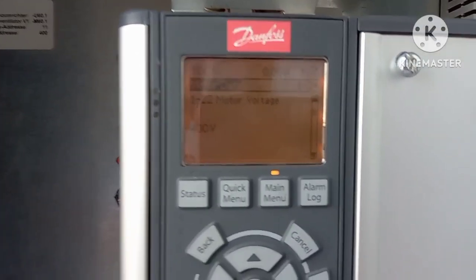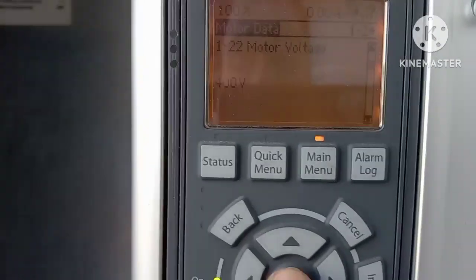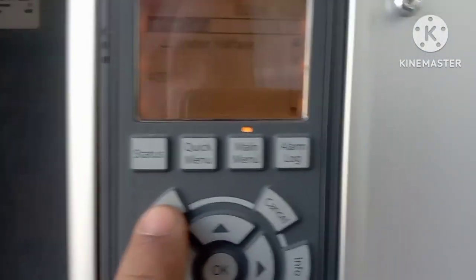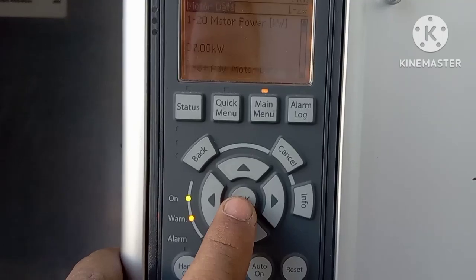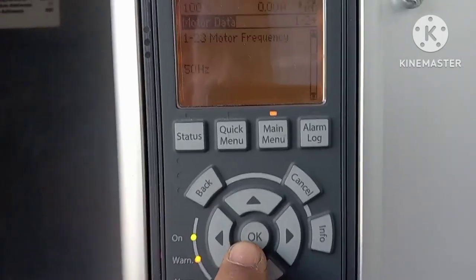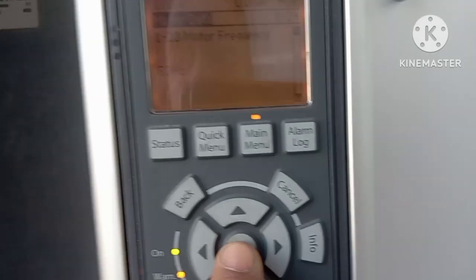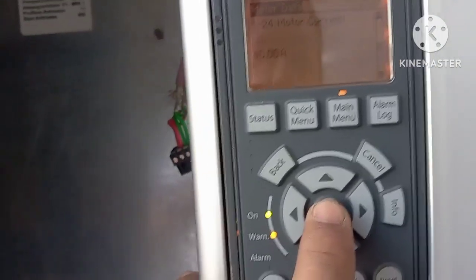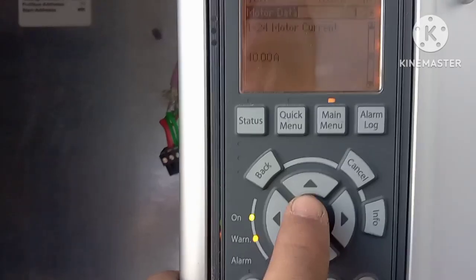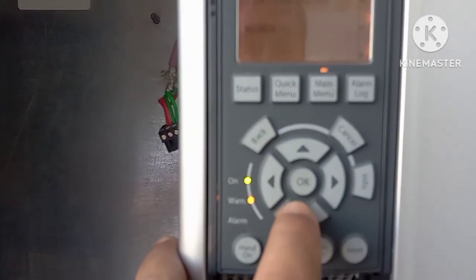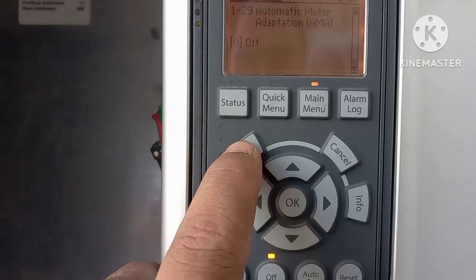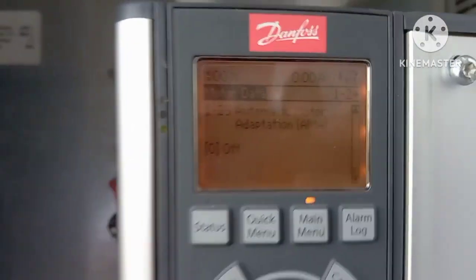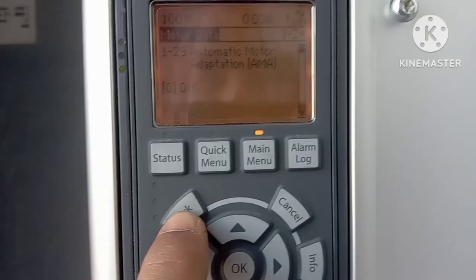Set motor voltage to the standard value. Motor frequency is 50 Hz — if you require 60 Hz you can set it accordingly. Motor current: the standard is 65 to 70 ampere, but for safety I am setting 40 ampere here. Then set the motor RPM. From here you can also automatically read the motor parameters.